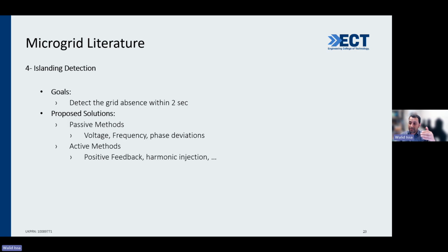Now, islanding means the grid is absent for some reason, and for detection, we need to detect whether the grid is absent. Our inverter should have some technology to discover the absence of the grid without communication. Again, we don't need to communicate with the grid, asking, oh, are you absent? No, we want to discover the absence of the grid within 2 seconds. Based on what? Based on the IEEE standard. The IEEE standard says an inverter should discover the absence of the grid without communication within 2 seconds. If the grid is absent, the inverter should take action to stop exporting power to the transmission line to make it safe, and maybe it has a technique to isolate itself and still supply the house. Okay, so that's called islanding detection.